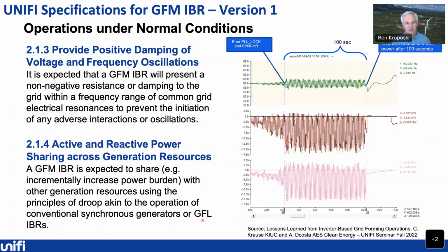In addition, we want to look at things like providing positive damping to voltage and frequency oscillations. I'll put a plug right in here for our UNIFI seminar series, which we also do on a very regular basis in the spring and fall. But this graph right here is from one of the recent talks from the Kauai Island Utility Cooperative. There's a place right now where we have an extremely high level of inverter-based resources, and probably one of the few places in the world that today is operating grid forming inverter-based resources on their system. One of the key things we want to make sure of is that as we add these inverters into the system, they have some type of damping once they start to see oscillations in the grid. One of the challenges we have right now is not necessarily understanding what all those possible oscillations would be. So we need to make sure that we're starting to build in a damping coefficient, if you will, against oscillatory behavior on the grid.